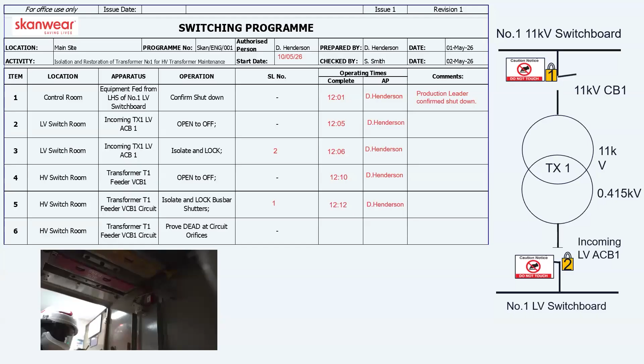Once we've isolated, we're going to prove dead, so we're going to do our live dead live checks. Once we've proven dead, we will then earth or ground that circuit to prevent induced voltages and discharge any capacitance in the cable or the primary windings. So that's the process, and we'll maintain that throughout. If there are any adjacent cables that are still energized, any inductance will discharge straight to ground or straight to earth.